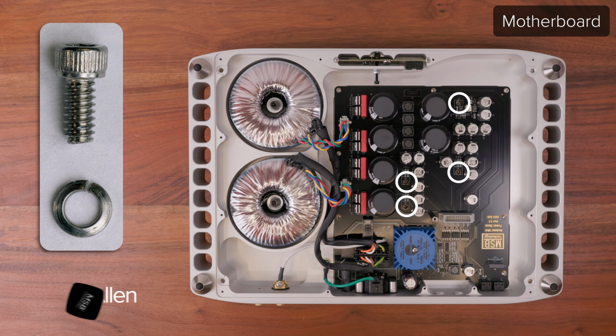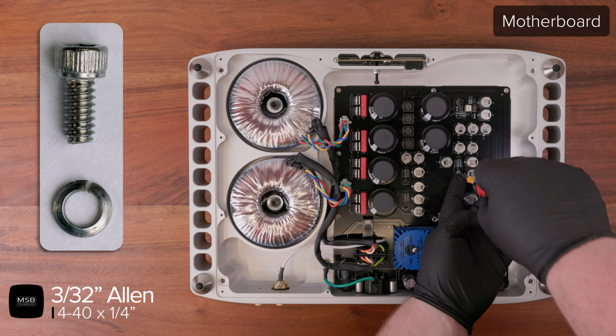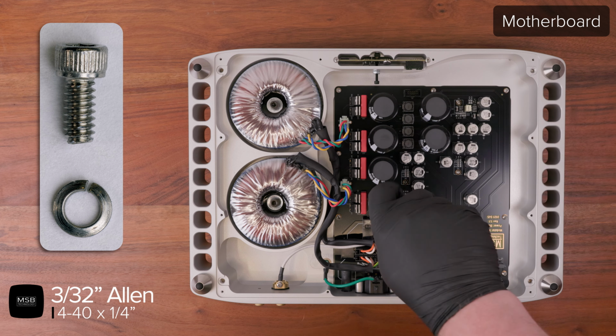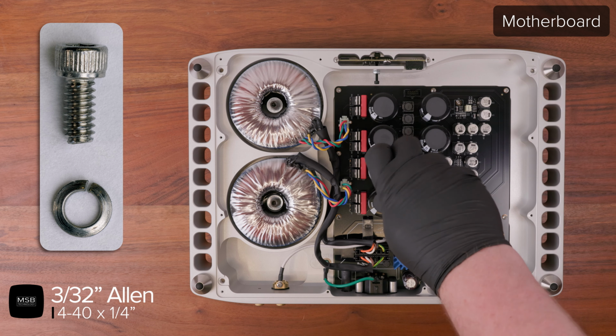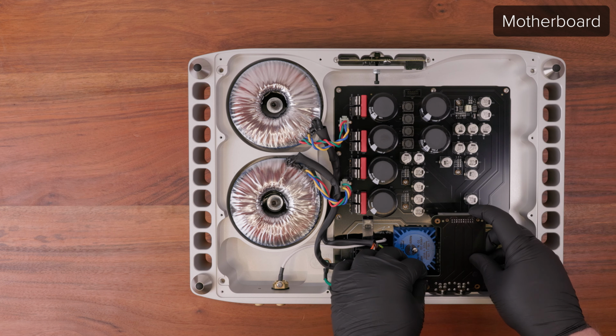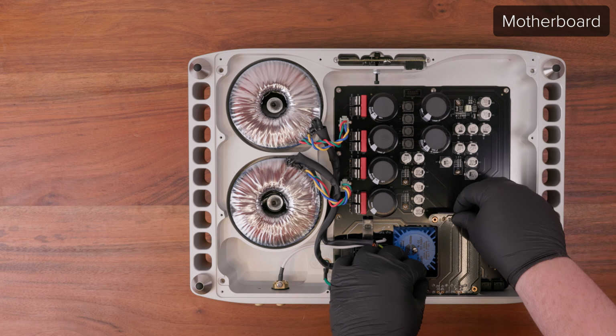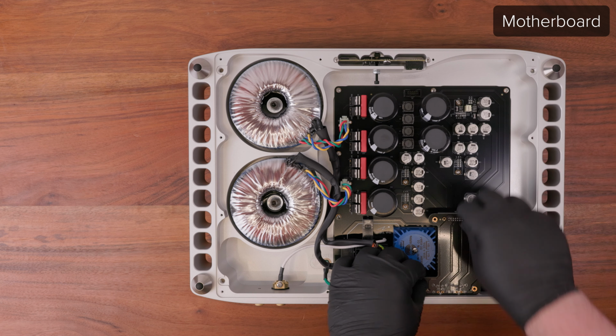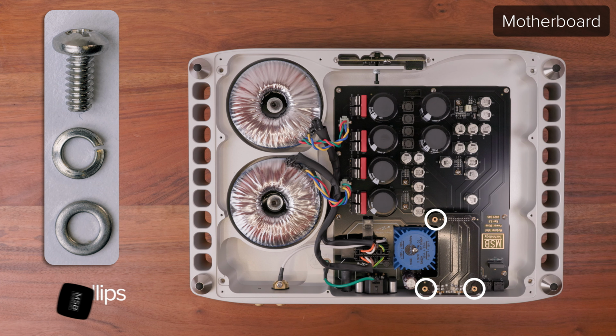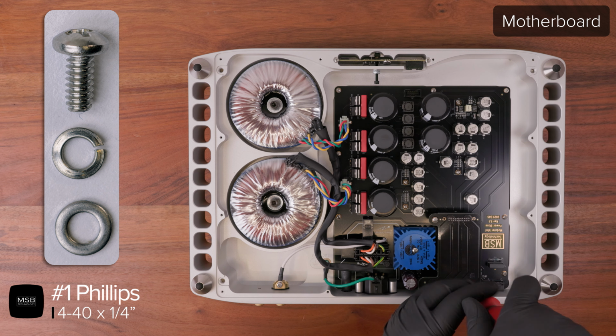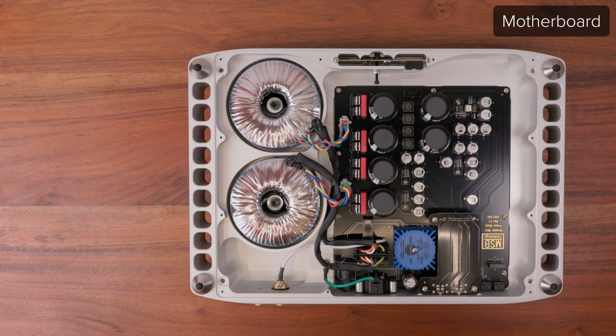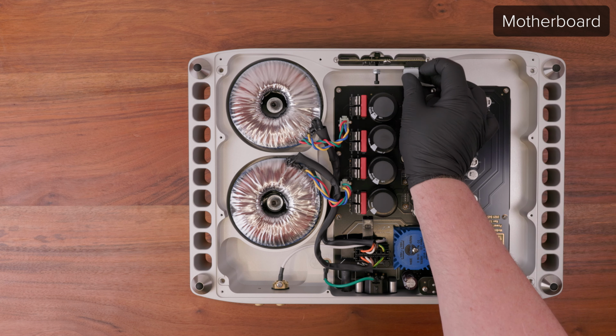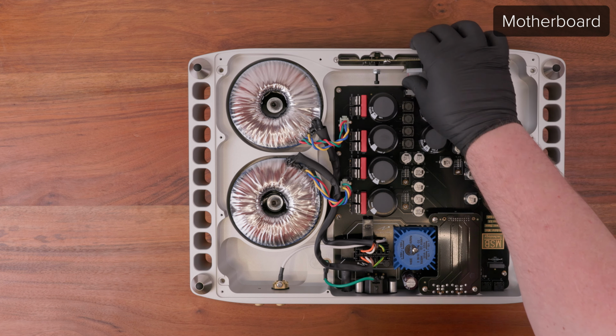Use a 3/32 Allen driver to replace the 4 4-40 device screws and lock washers. Do not over-tighten these screws. They just need to be tight enough to flatten the lock washer and push the device against the chassis. Replace the small DC connector board by guiding it into the jack panel and then seating the connector at the back. Then use a number 1 Phillips to replace the 3 4-40 board screws and washers around the board. Replace the ribbon cable at the front of the product in the following orientation.